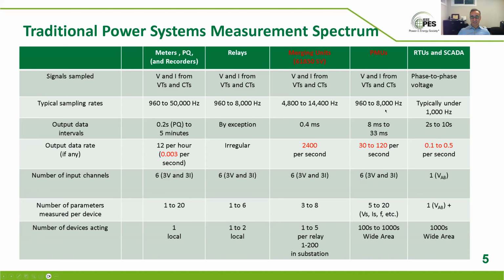PMUs come in as phasor measurement units. You could imagine they're the next generation of part of SCADA. SCADA is supervisory control and data acquisition. PMUs are the data acquisition side of it. They're not the control part of it, of course. There you measure voltage and current, not just voltage, often enough. And the device itself samples at higher frequency, but usually once or maximum twice per cycle is the communication rate or the data rate to provide phasors. There are systems that can do even faster, but often enough with phasors, you're looking at per cycle. It kind of makes sense because the standard focuses on power frequency only, 60 or 50 hertz. And if you go to sub-cycle, well, it is an estimation and it's a fit.